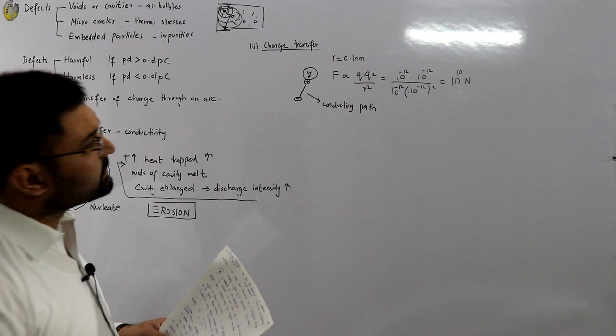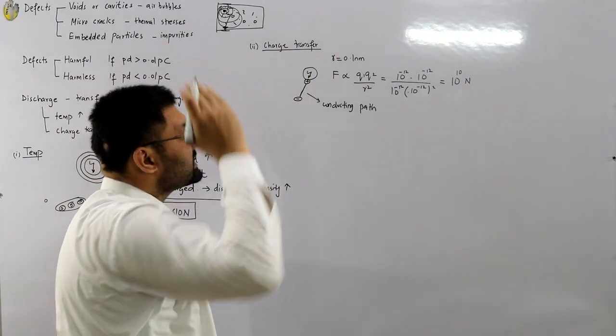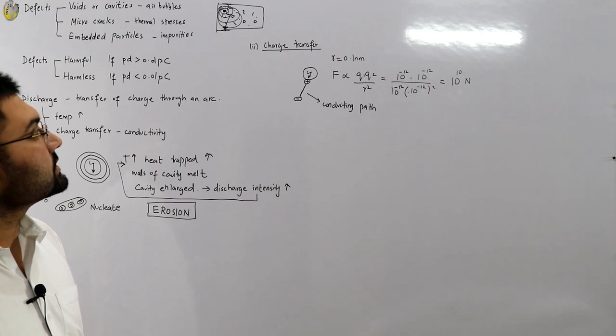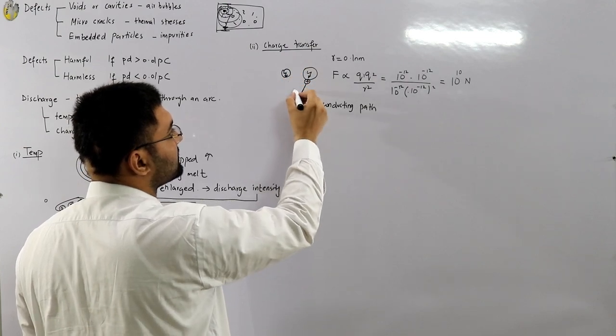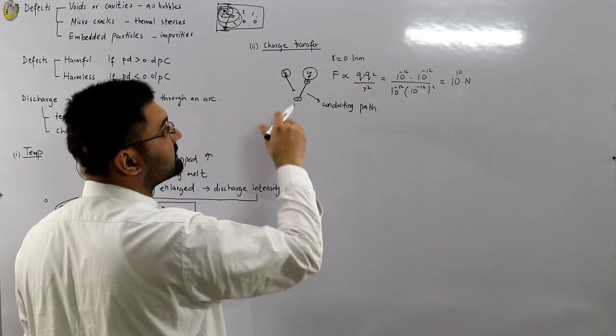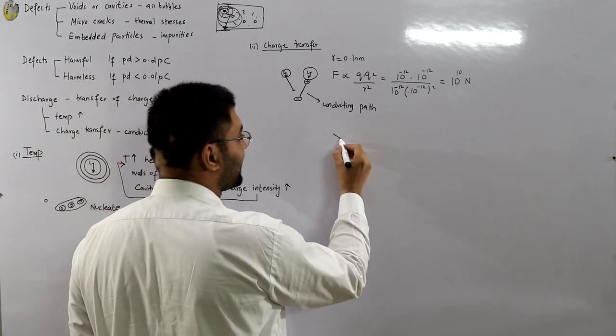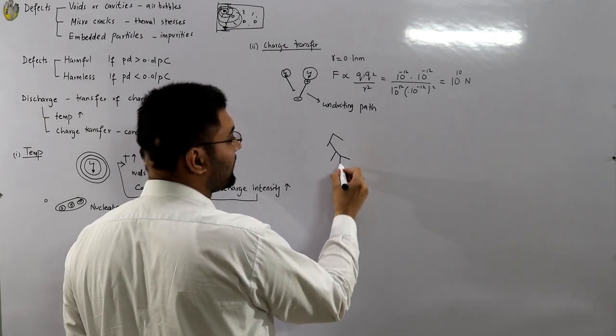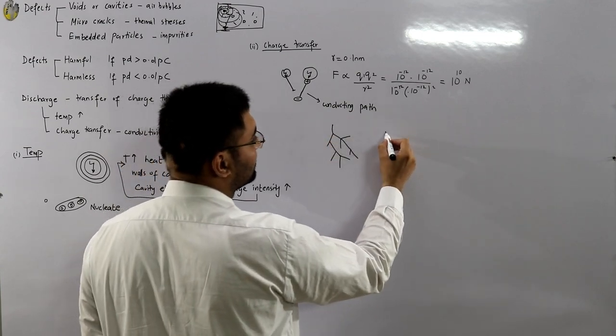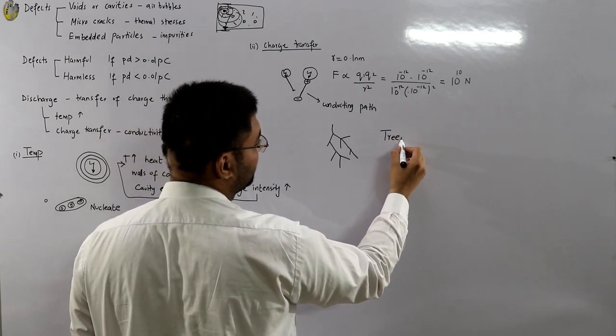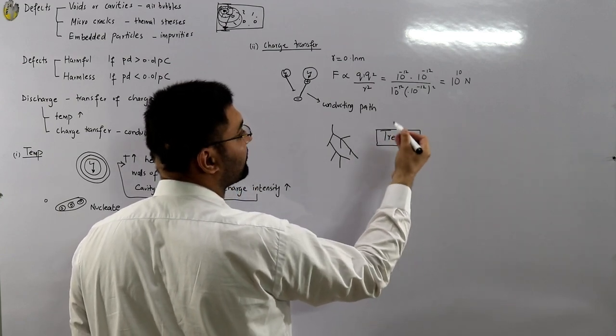This conductive path formed by the attraction of opposite charges is called tracking. Multiple discharge events across different voids form multiple tracks. From observations, these tracks appear as fine channels in the form of a tree-like structure. This process is therefore called treeing.